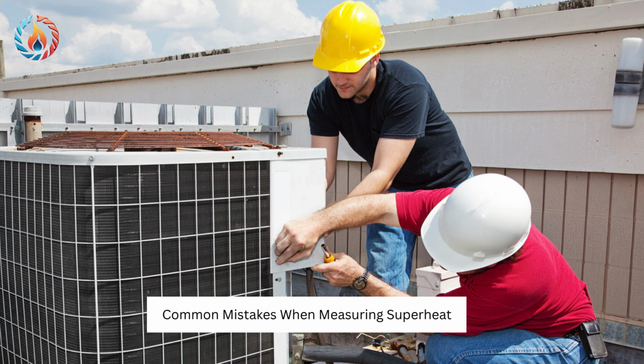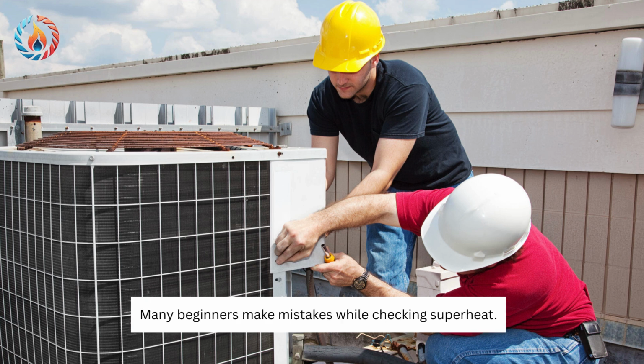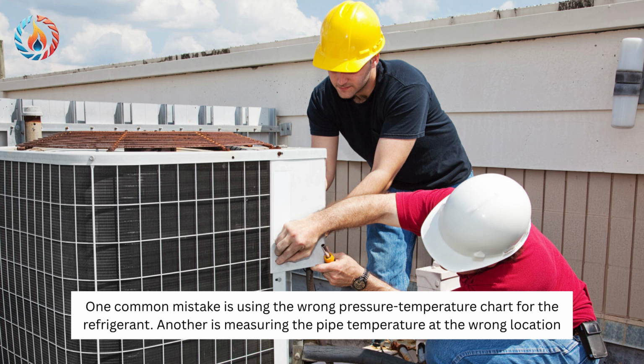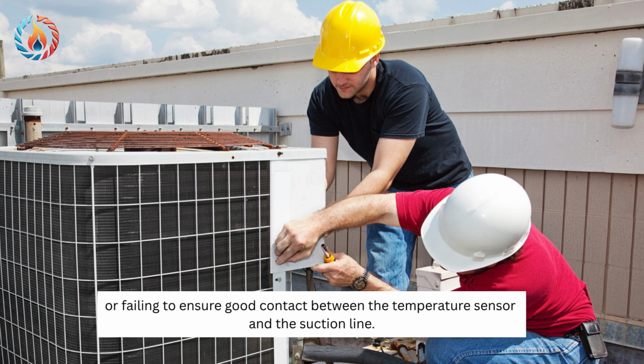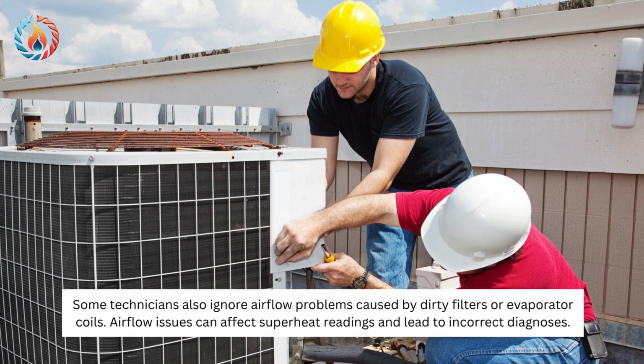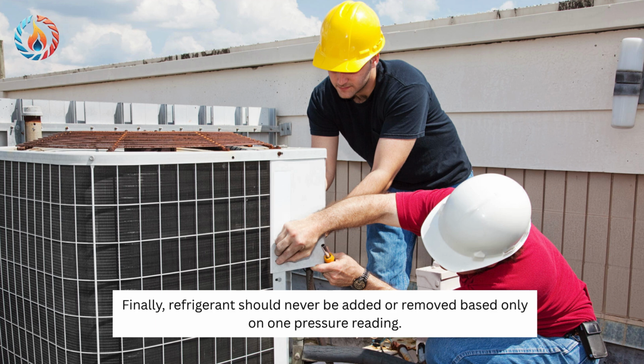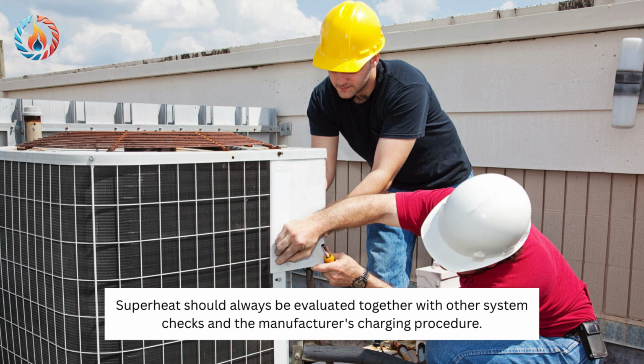Common mistakes when measuring superheat. Many beginners make mistakes while checking superheat. One common mistake is using the wrong pressure temperature chart for the refrigerant. Another is measuring the pipe temperature at the wrong location, or failing to ensure good contact between the temperature sensor and the suction line. Some technicians also ignore airflow problems caused by dirty filters or evaporator coils. Airflow issues can affect superheat readings and lead to incorrect diagnoses. Finally, refrigerant should never be added or removed based only on one pressure reading. Superheat should always be evaluated together with other system checks and the manufacturer's charging procedure.